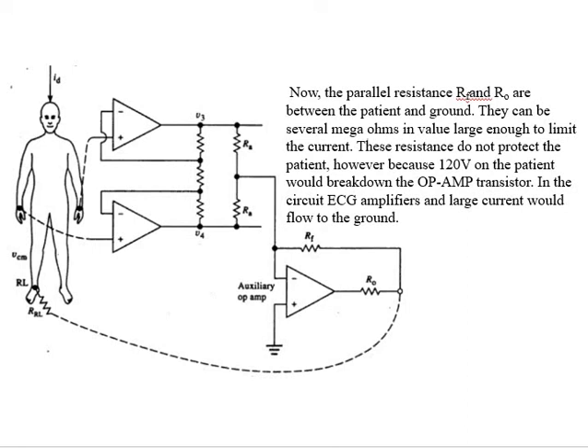The parallel resistances Ra and Ro are between the patient and ground, with values of several megaohms — large enough to limit the current. As mentioned, if there is a very high resistance, the current flow through that resistance is kept under control, very low or minimum. If this is the case, then we can pick the signals at both arms.